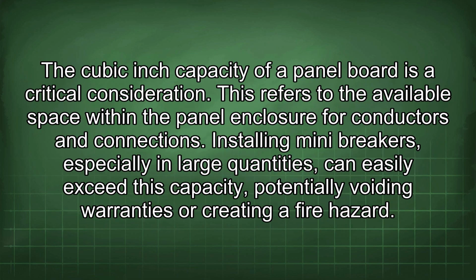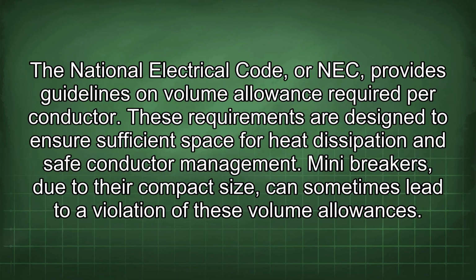The cubic inch capacity of a panel board is a critical consideration. This refers to the available space within the panel enclosure for conductors and connections. Installing mini breakers, especially in large quantities, can easily exceed this capacity, potentially voiding warranties or creating a fire hazard. The National Electrical Code, or NEC, provides guidelines on volume allowance required per conductor. These requirements are designed to ensure sufficient space for heat dissipation and safe conductor management. Mini breakers, due to their compact size, can sometimes lead to a violation of these volume allowances.